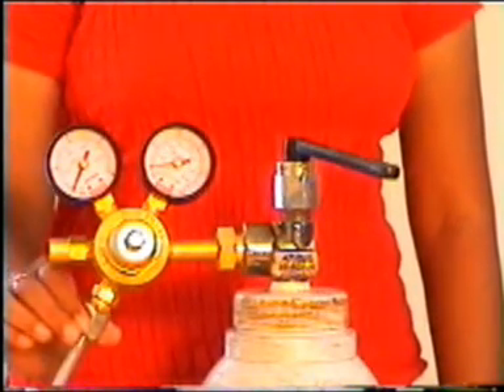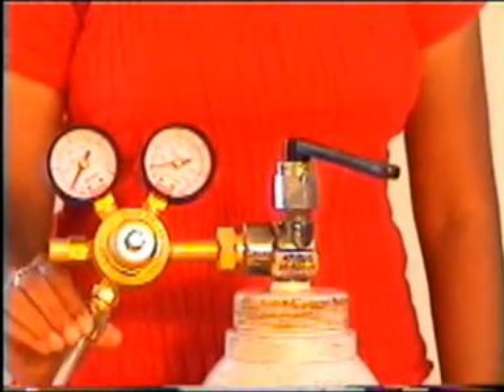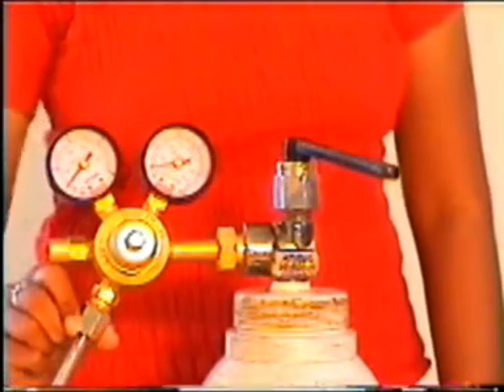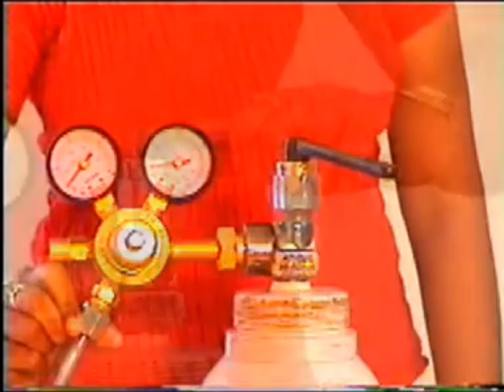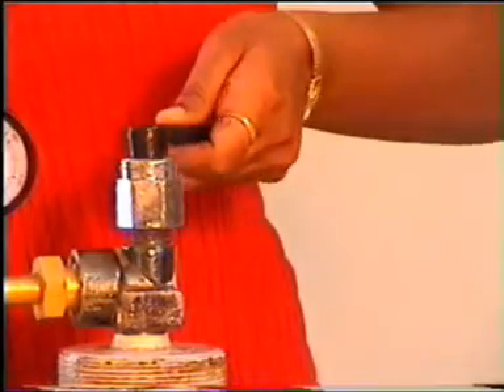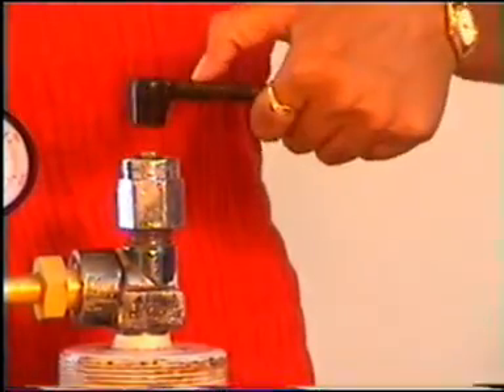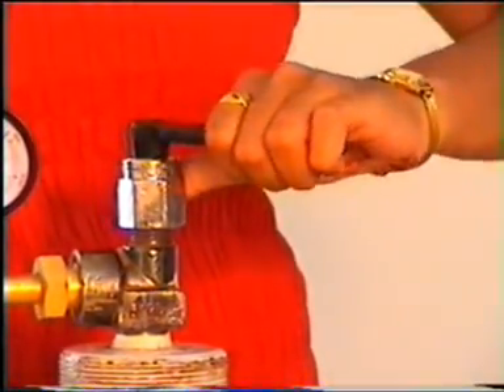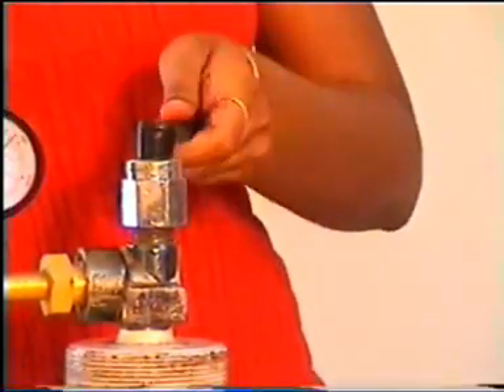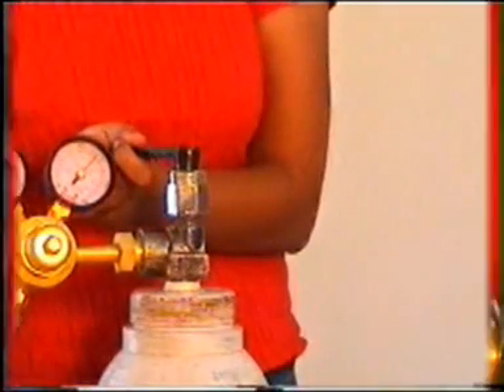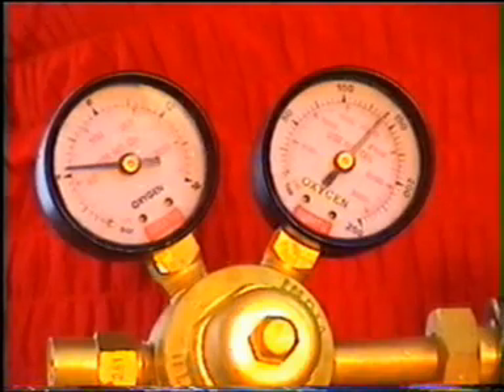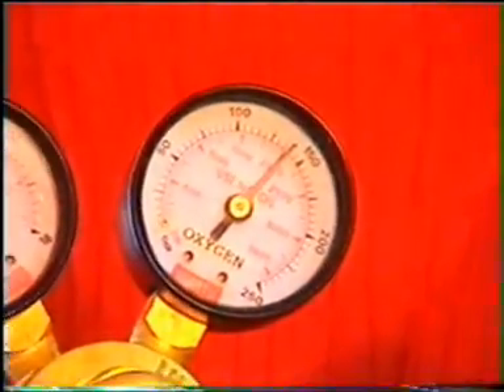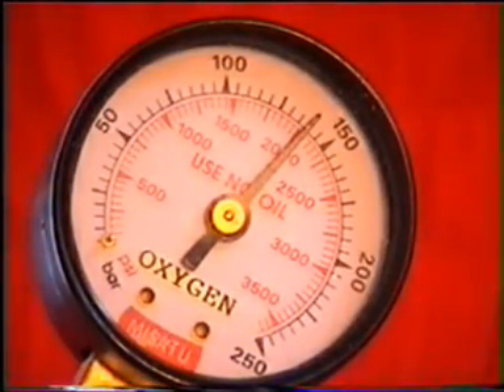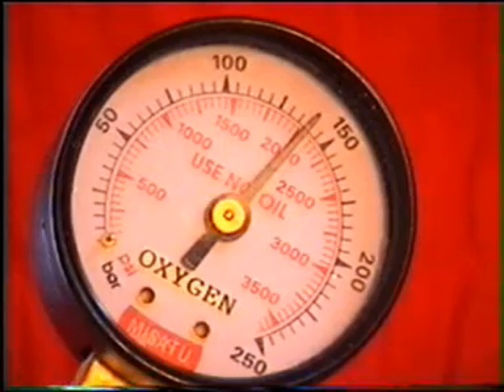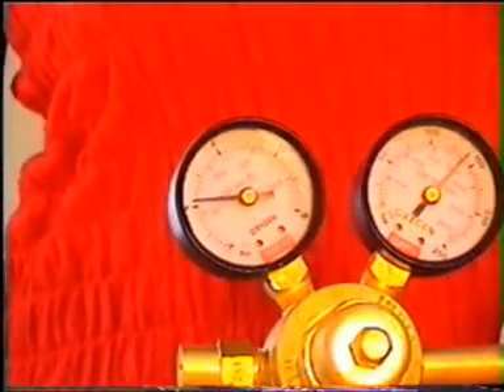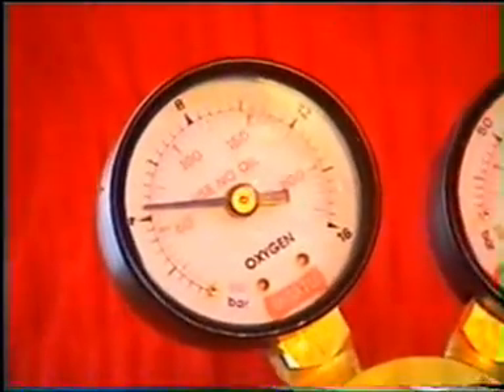The regulator end of the inlet gas tubing is screwed over the regulator and tightened securely. The oxygen cylinder is opened. The right-hand side meter shows the cylinder status. See that the sufficient quantity of oxygen gas is available in the cylinder. The left-hand side meter shows the secondary regulated pressure, which is about 4 kg per square centimeter.